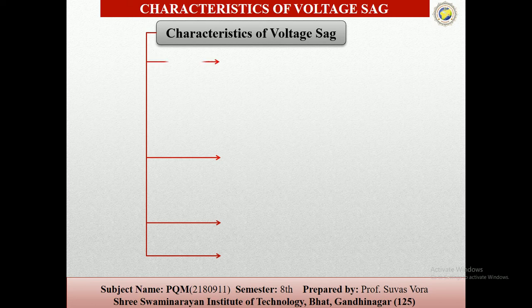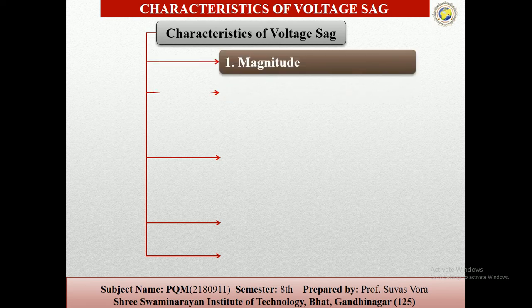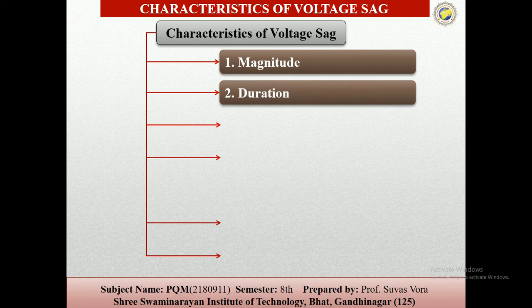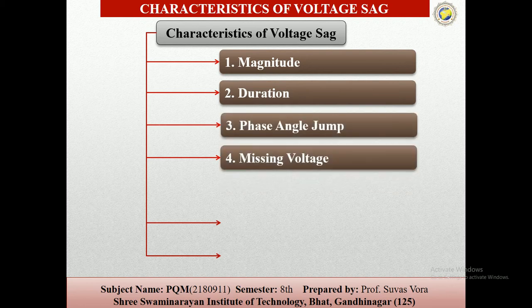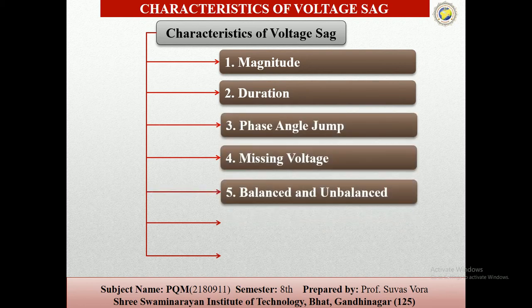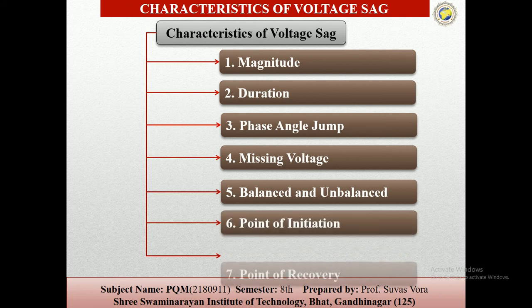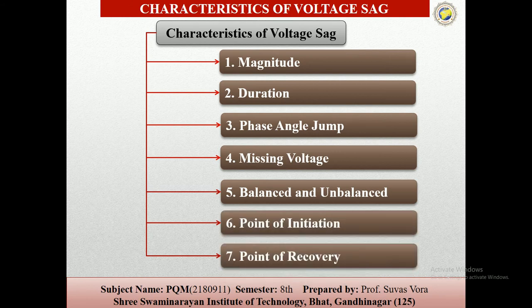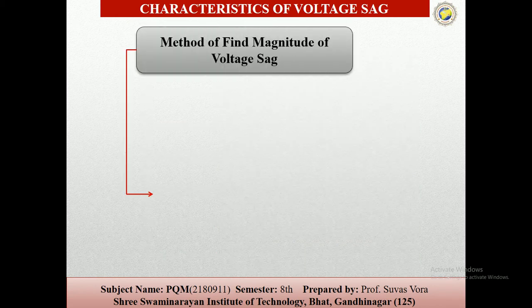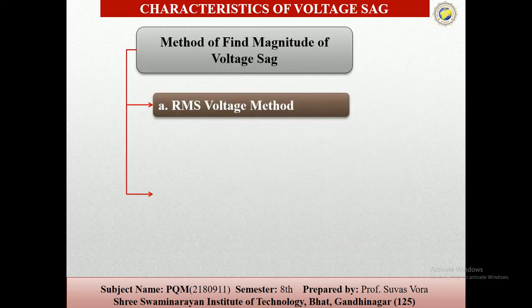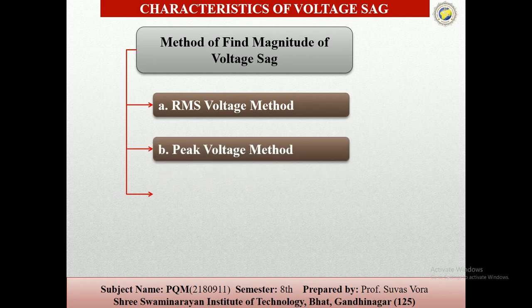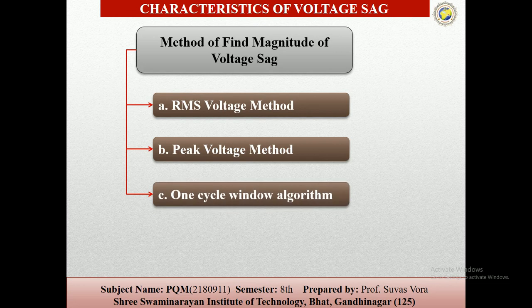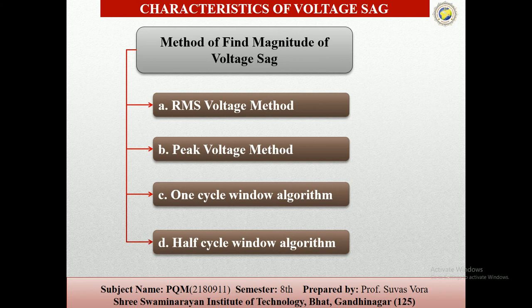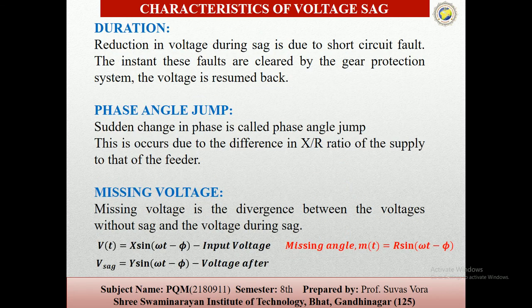Then the characteristics of the voltage sag: magnitude, duration, phase angle jump, missing voltage, balanced and unbalanced conditions, then point of initiation and point of recovery. For the method of calculation, the magnitude of the voltage sag depends on the RMS voltage method, then the peak voltage method, then the one cycle window algorithm, and the last one is the half cycle window algorithm. So these are the durations.